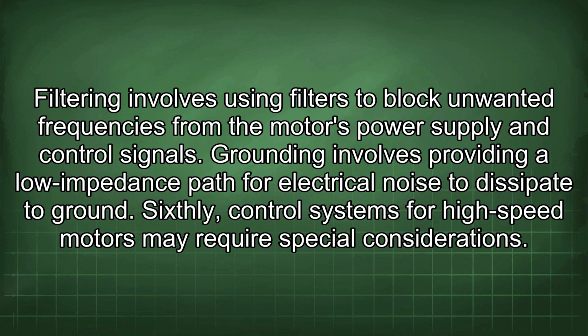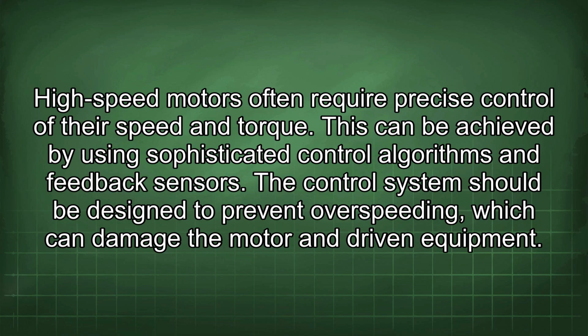Sixthly, control systems for high-speed motors may require special considerations. High-speed motors often require precise control of their speed and torque. This can be achieved by using sophisticated control algorithms and feedback sensors. A control system should be designed to prevent overspeeding, which can damage the motor and driven equipment.